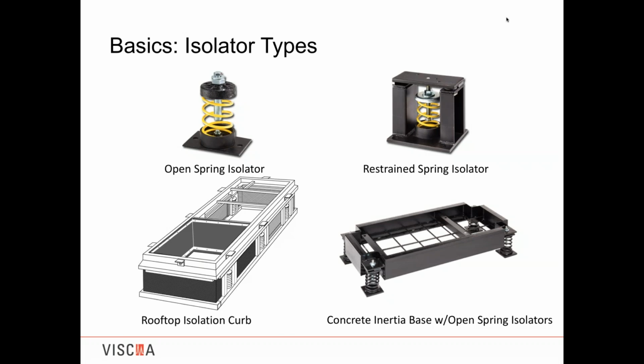Some of them, this one shown in the picture, come with a base plate. You can anchor it down to building structure. Not designed for shear, it's just designed so it doesn't walk on you over time. The next one on the upper right is restrained. It's also a category of housed spring isolators. The welded design and the restrained are typically for wind and seismic outdoor applications when they're galvanized instead of painted. What they offer is spacing. It's hard to see in the image, but it's spacing for concrete anchorage when you're going into concrete. So for tip over, your anchors aren't spaced too closely. You can get some rating out of it. Some of them are designed for blocking during shipping.